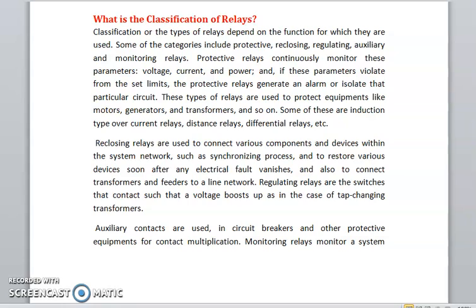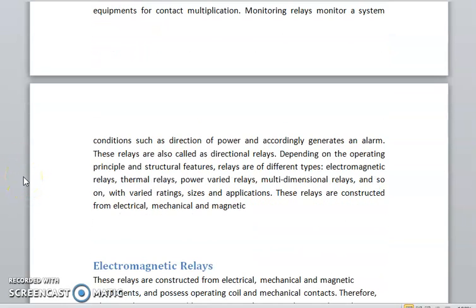Reclosing relays are used to connect various components and devices within the system network, such as in the synchronizing process, and to restore various devices soon after any electrical fault vanishes, and also to connect transformers and feeders to a line network. Regulating relays are the switches that contact such that a voltage boost up, as in the case of tap changing transformers. Auxiliary contacts are used in circuit breakers and other protective equipment for contact multiplication. Monitoring relays monitor a system condition such as direction of power and accordingly generate an alarm. These alarm relays are also called directional relays.